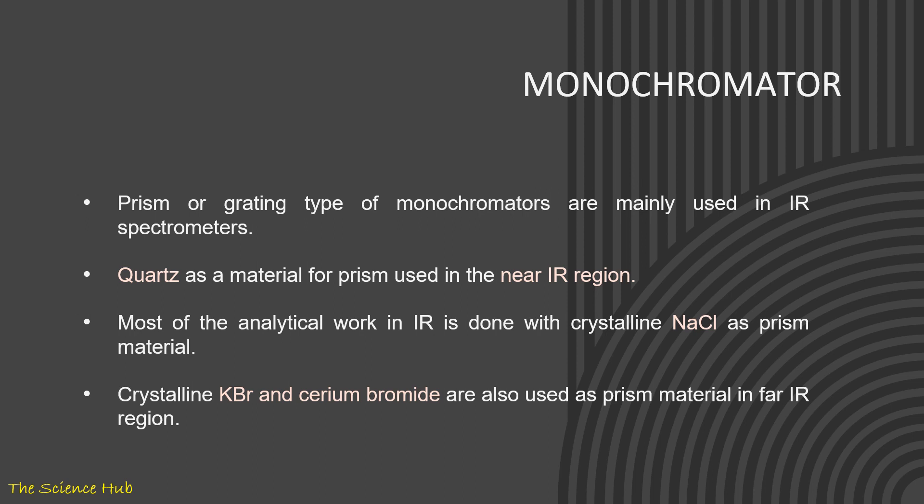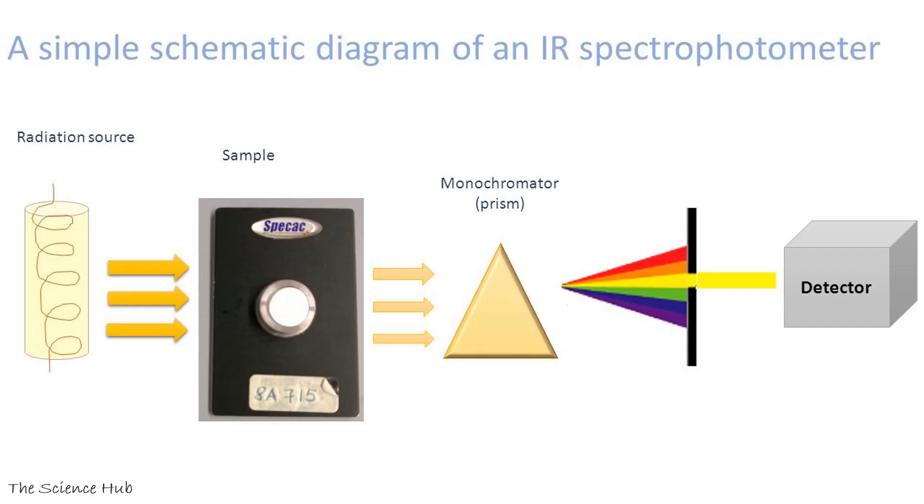Here you can observe all instrumentation. First, radiation source is there. From radiation source, IR lights or radiations are coming out and incident to the sample. Sample absorbs that radiation and remaining frequencies, remaining wavelengths come out from that. And monochromator will disperse the radiation and we'll get particular frequencies which will be detected and interpreted by detector and recorder.